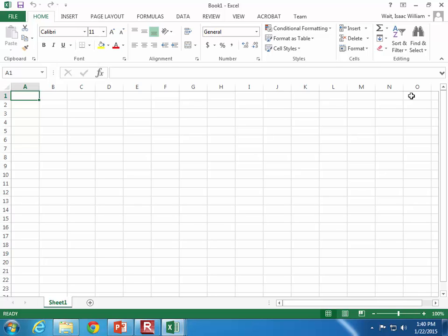All right, so let's do this. There's horsepower, which I knew was 10. There's the K sub S value in terms of feet. This is the equivalent sand roughness. If I look that up in the table that's provided in the book, this pipe has a roughness of 0.00085.